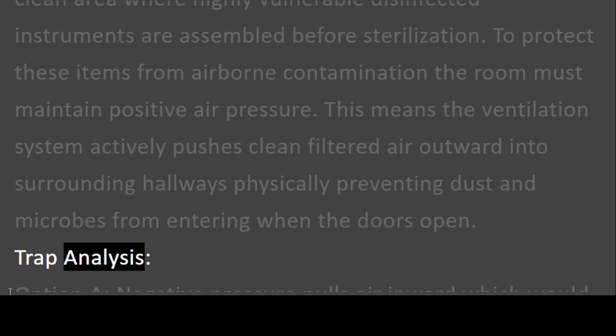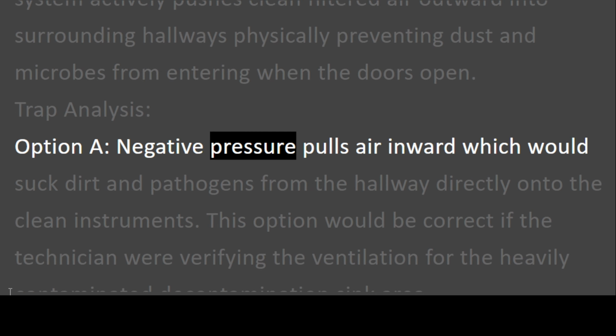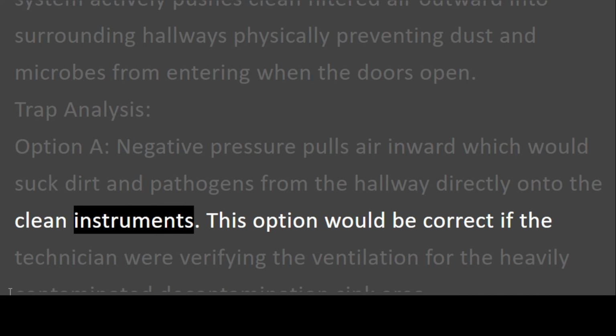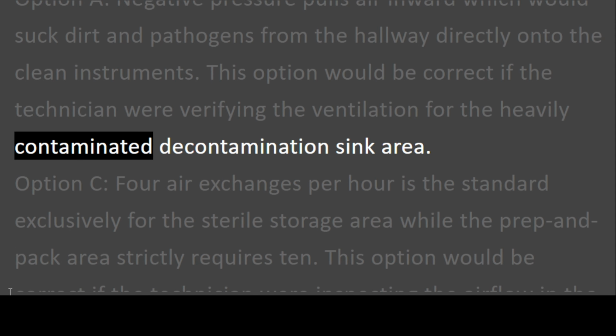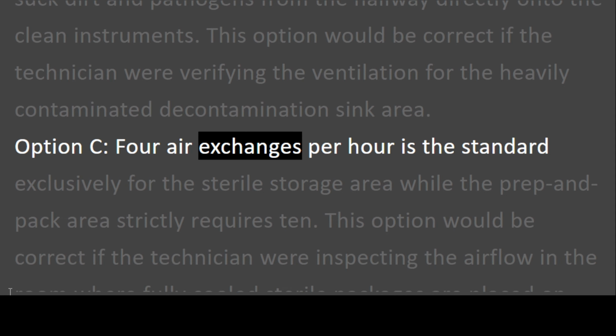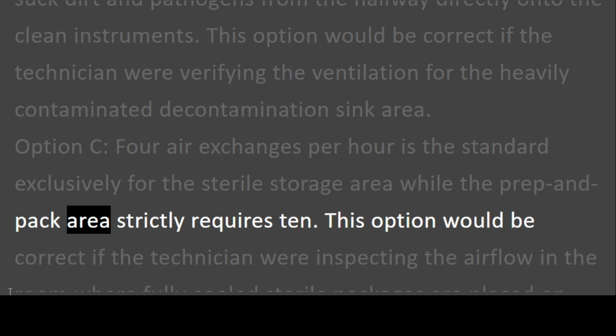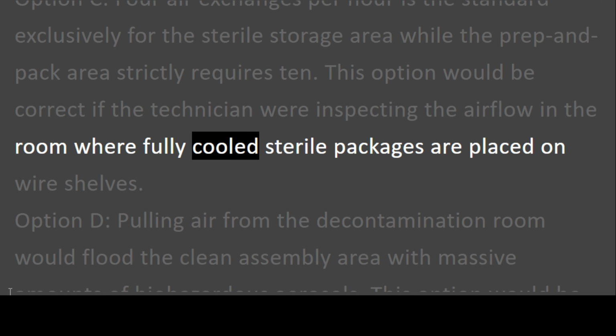Trap analysis. Option A. Negative pressure pulls air inward, which would suck dirt and pathogens from the hallway directly onto the clean instruments. This option would be correct if the technician were verifying the ventilation for the heavily contaminated decontamination sink area. Option C. 4 air exchanges per hour is the standard exclusively for the sterile storage area, while the prep and pack area strictly requires 10. This option would be correct if the technician were inspecting the airflow in the room where fully cooled sterile packages are placed on wire shelves.